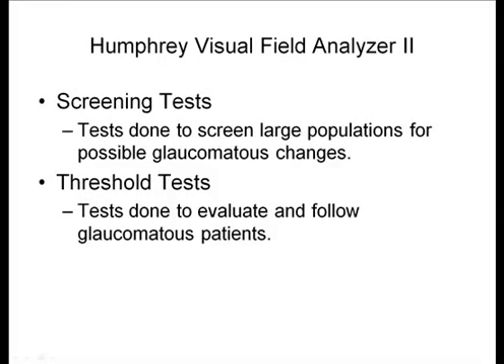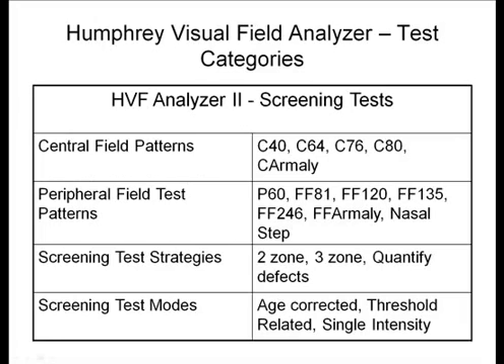There are two basic types of tests on a Humphrey visual field: screening tests and threshold tests. Screening tests are done to look at large numbers of patients or populations for possible glaucoma changes. They're not sensitive enough or don't bracket threshold enough to follow patients long-term for glaucoma. Several screening tests are available on the Humphrey Field Analyzer 2, but they are not typically used in practice.